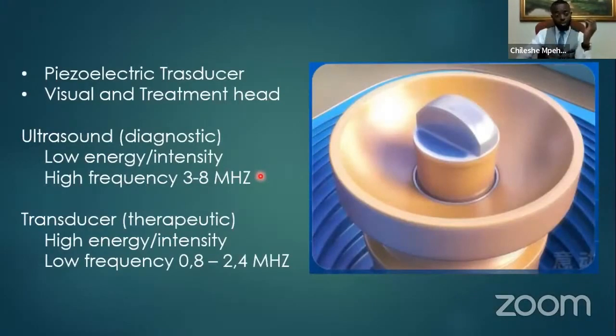Now, when we want to treat, we don't want those sound waves traveling all the way through; we prefer them to get trapped and vibrate in the tissues. So our therapeutic transducer uses high energy but sends the sound waves at a slower frequency of 0.8 to 2.4 megahertz. By slowing down those sound waves, we actually get to treat.